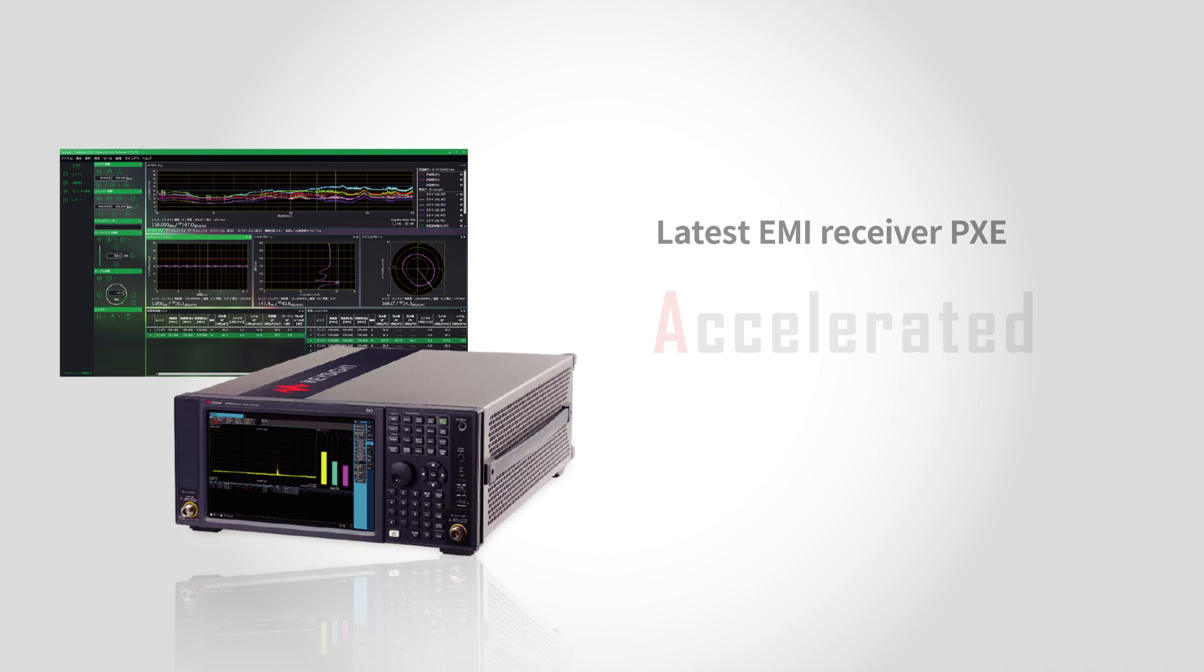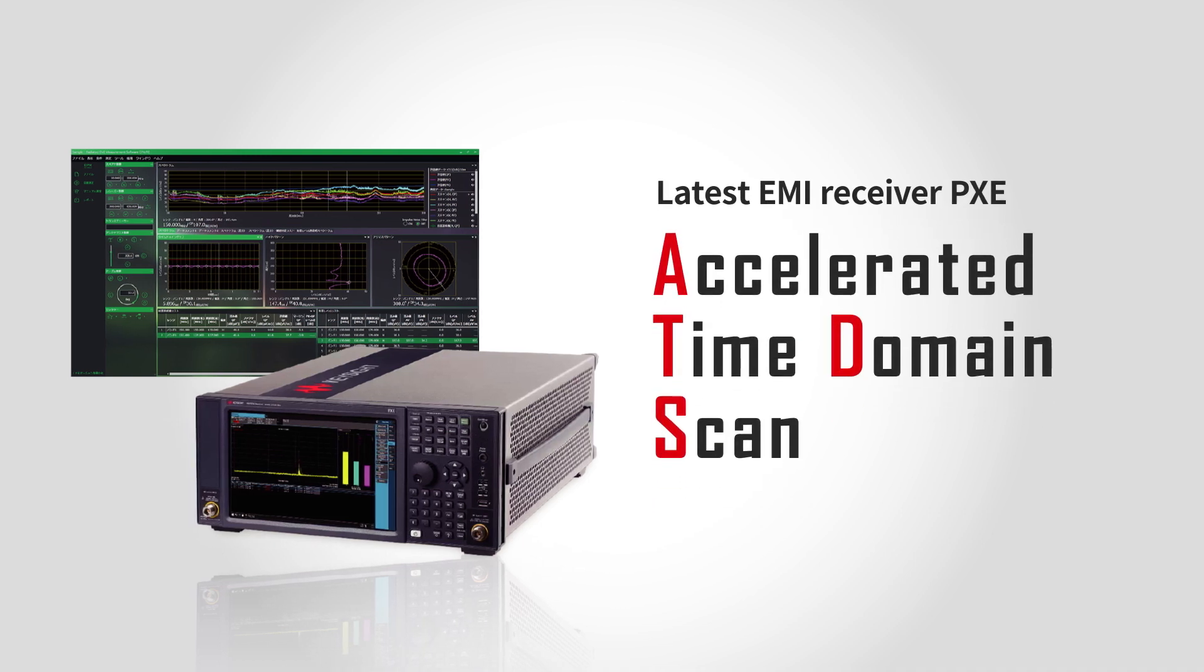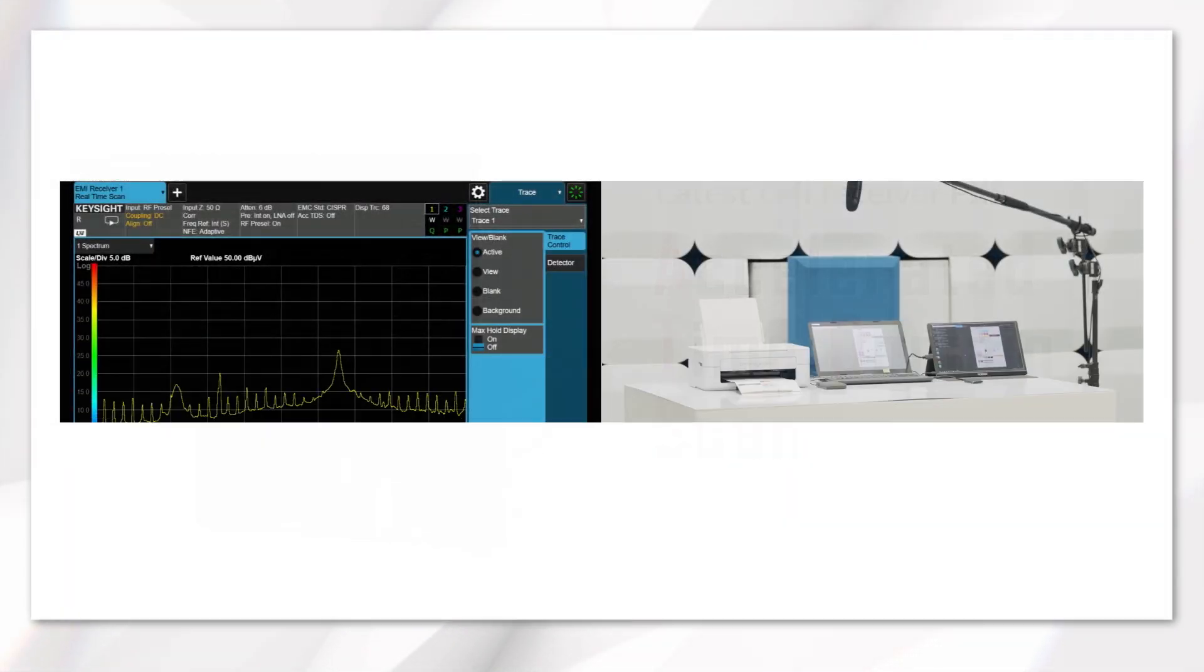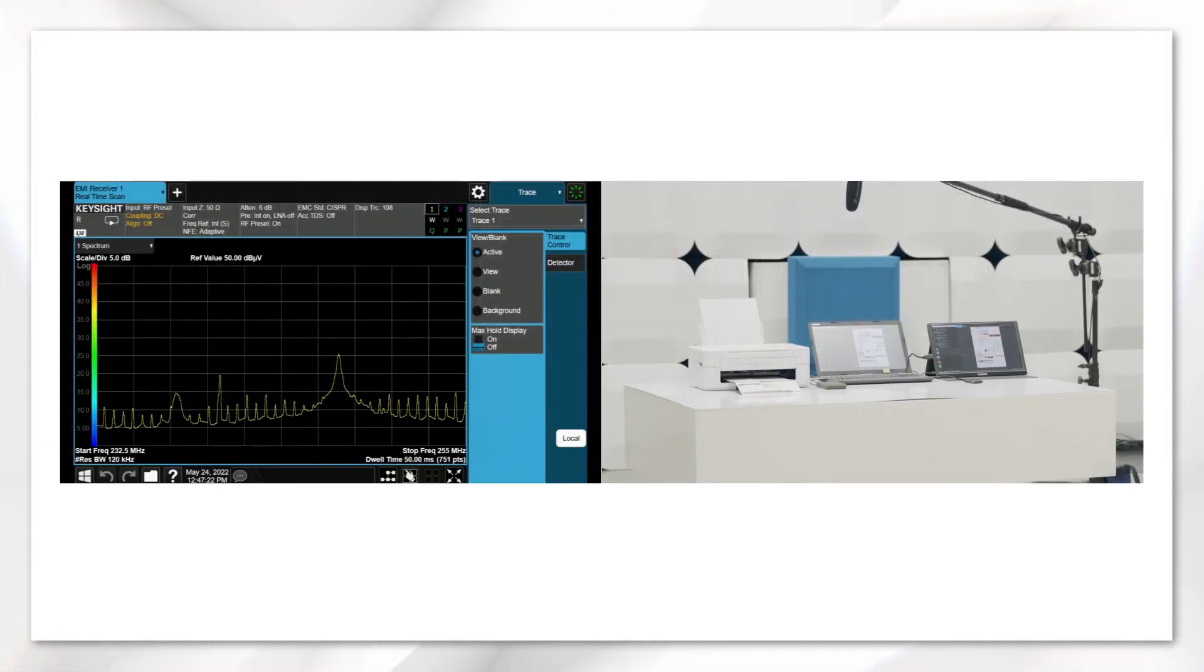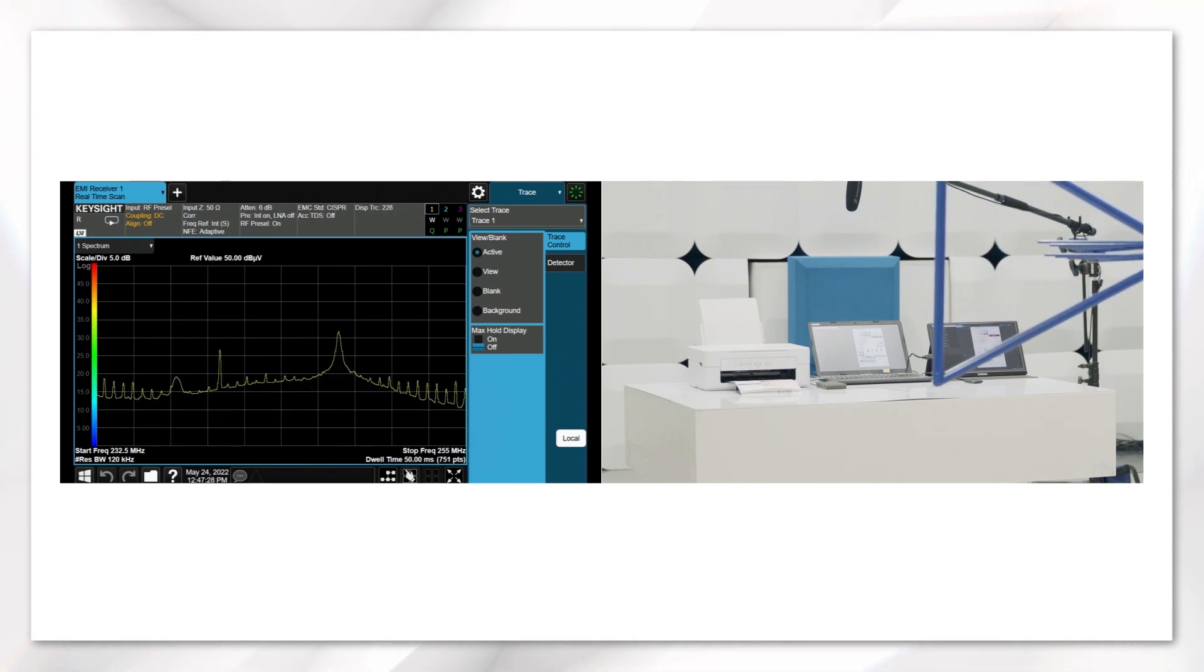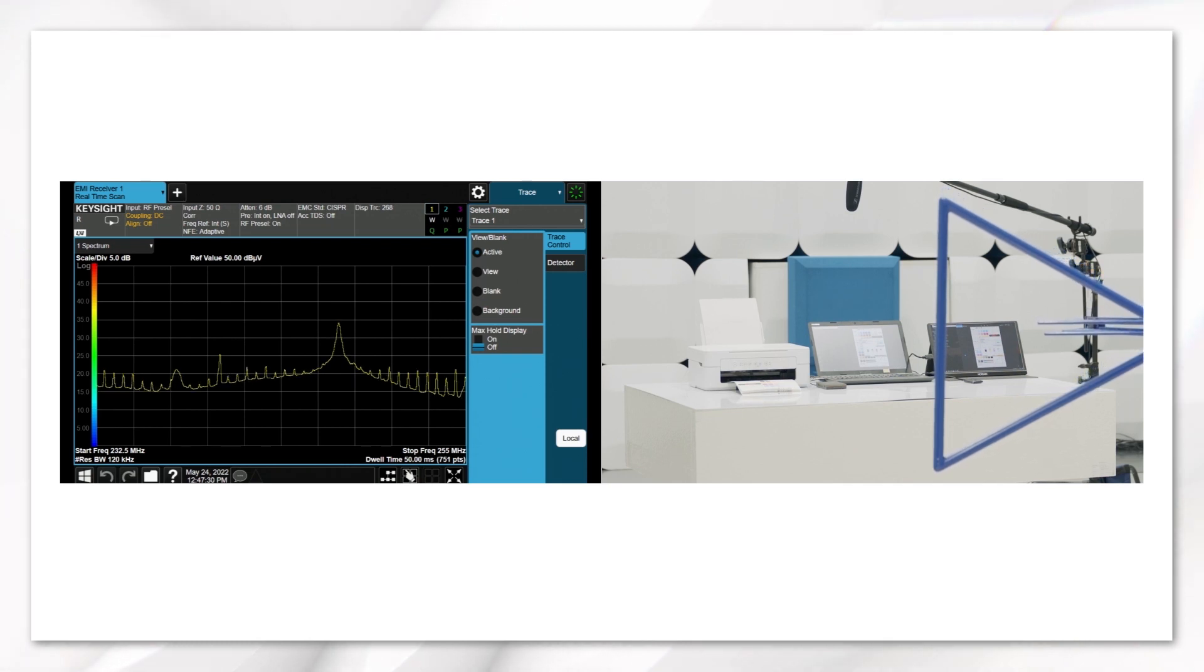The Accelerated Time Domain Scan on the PXE can address these challenges at compliance measurement. With the PXE, you can accurately determine the peak noise levels with just one measurement. That is because it gaplessly monitors the noise in the suspect list at all times.